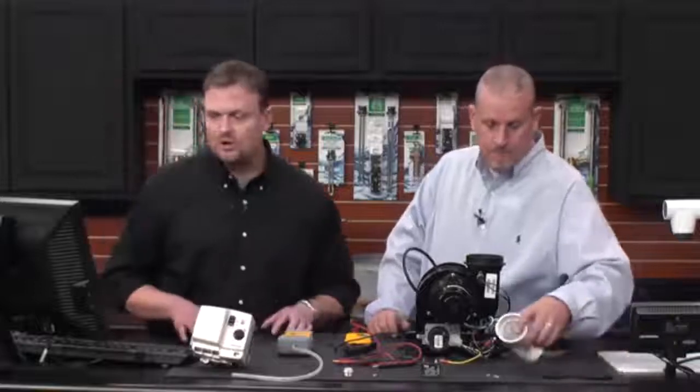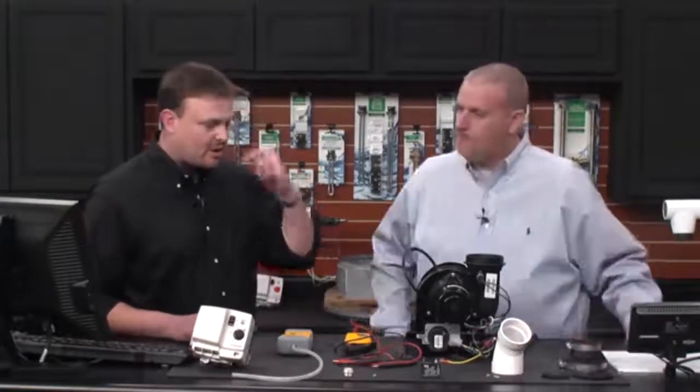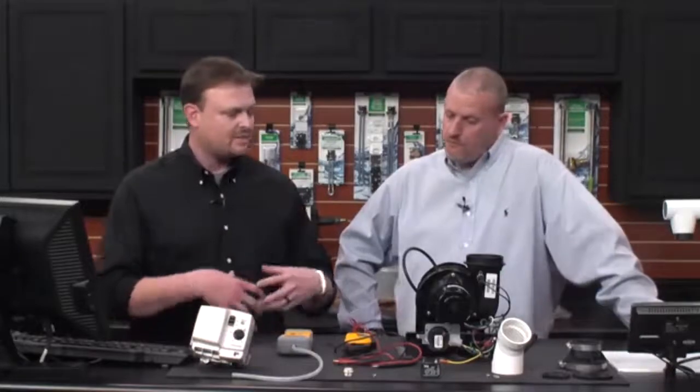The next code I want to talk about is a 6.3 error code. It means that the unit fired, it's running, and then all of a sudden we lost flame. It's a flame loss error code, a 6.3. And really looking at it, we're going back to the same thing.